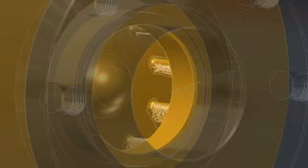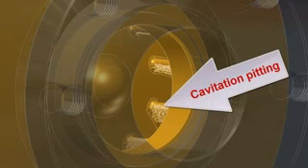This area is known as the eye of the impeller. And if I pause the impeller for a moment, we can see some evidence of cavitation damage modeled into the impeller, as shown here.